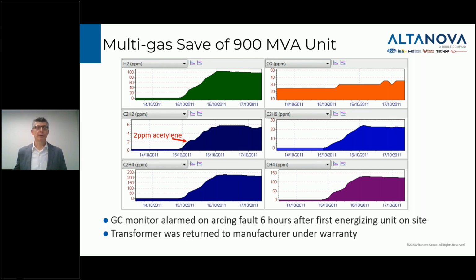Within the first 6 hours, fault gases started appearing at a significant rate. For example, the top plot in green shows hydrogen increasing from 0 to about 100 ppm over the course of a day. Below that is acetylene, which increased from 0 to about 6 ppm over the same day. We got the call on this unit right around when the acetylene had reached 2 ppm.